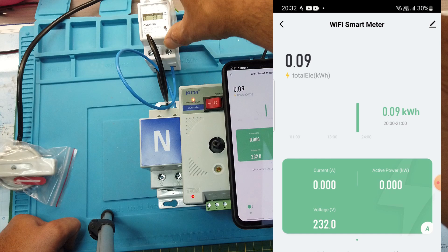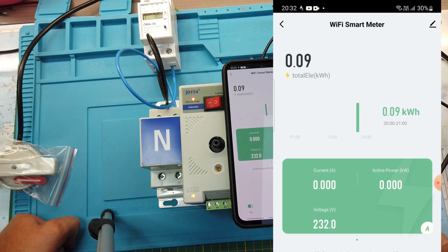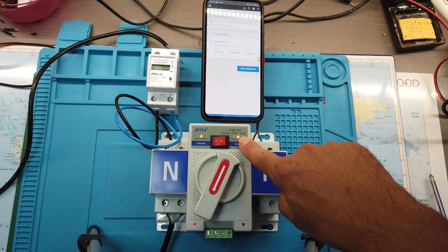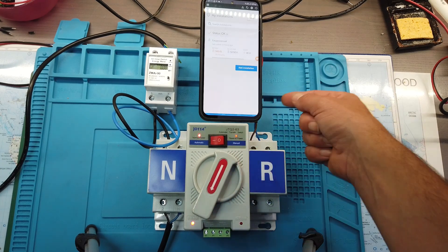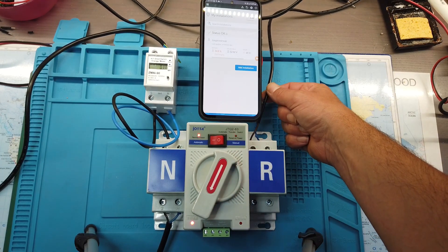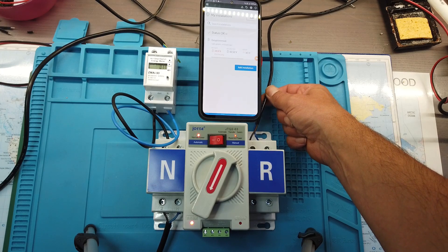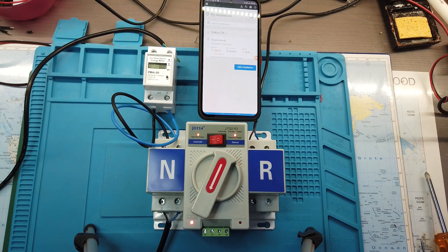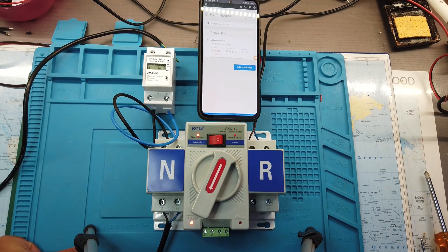The new model has a slightly modified interface, but I like the design — it looks really nice. Let's connect the power to the other socket and see what happens. As you can see, both lights are activated: normal power and reserve power. That means all lines are hot — they're both connected to mains. So we have 220 volts on every side of the ATS.